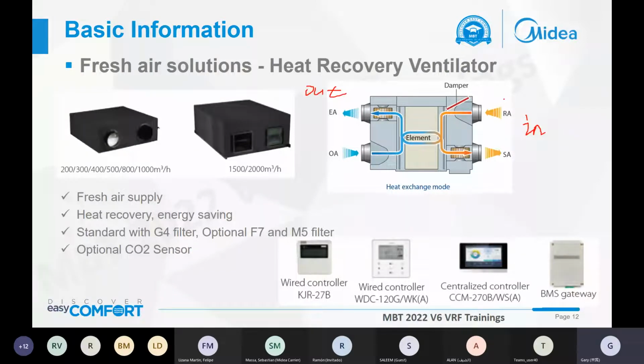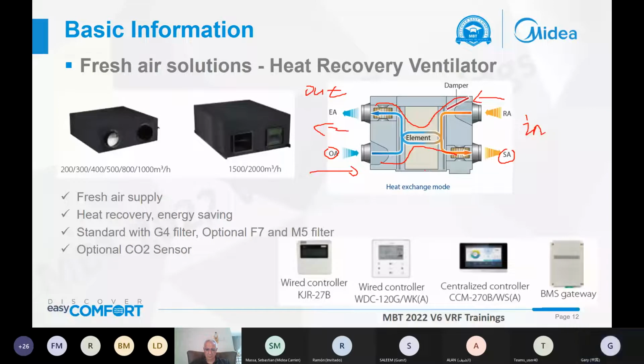The return air from this port discharges to the outside from this point, and the fresh air inlet is at this point, separate from it. So they will have a heat exchange in the elements. The fresh air will be cooled or heated by the return air, so the fresh air will be closer to the return air in temperature. So this part can save our energy.